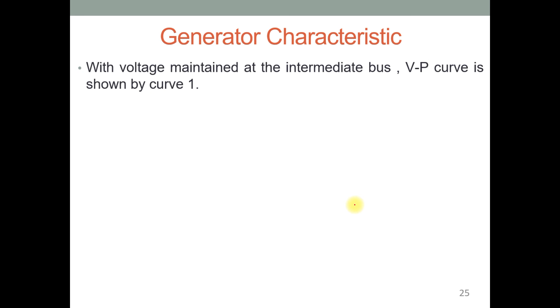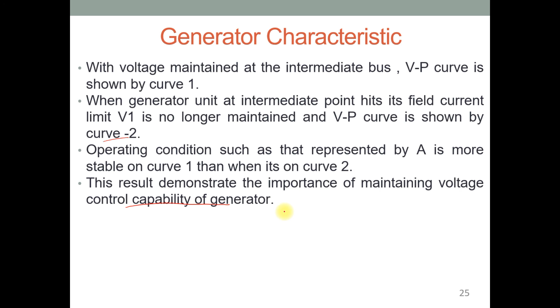Here, what I have explained is written here: when the generator reaches its field current limit, it can no longer maintain a constant voltage, which is shown by curve 2. That is, the generator will act as a constant current source. So the result demonstrates the importance of maintaining the voltage control capability of the generator. Clear? So that you can improve the generator terminal voltage for voltage stability analysis. I hope you are clear up to this.